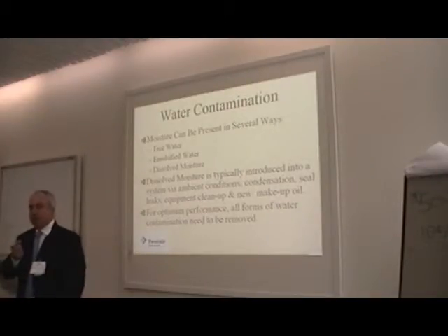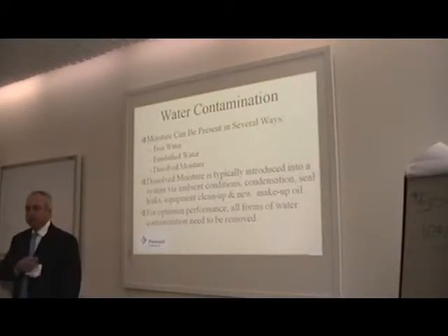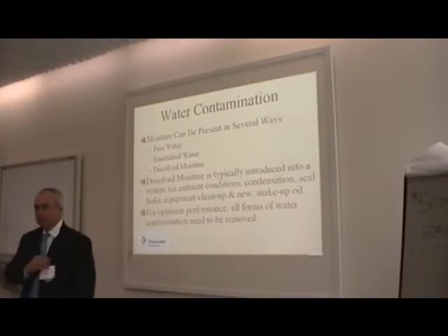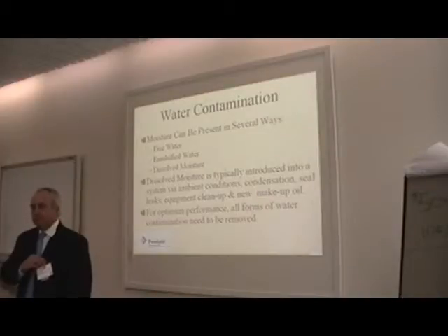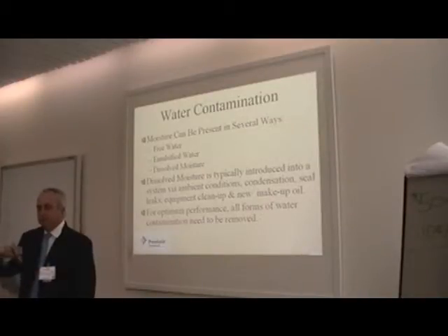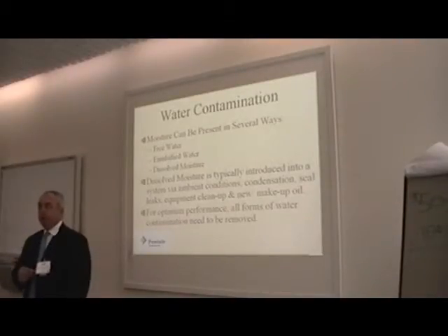You said that water was definitely an issue. Are you doing your own oil analysis or do you send it out? We've done both. We've done it internally, and as a check we've had it sent outside. Okay, because some of the systems don't really see water at a very low level. A lot of the little mini labs they put in plants have about 1,000 parts per million as their resolution, which in a turbine oil is very high already.